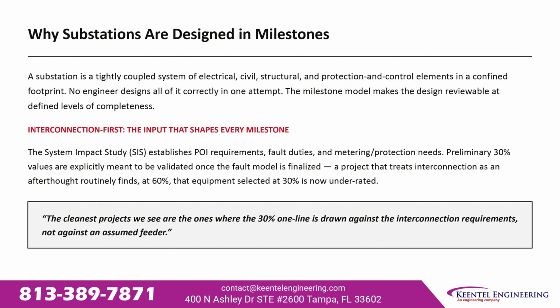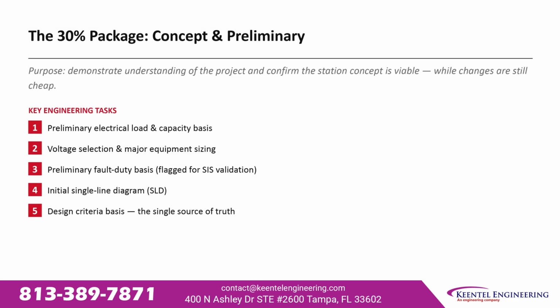The input that shapes every milestone is the interconnection. The System Impact Study establishes point of interconnection requirements, fault duties, and metering and protection needs. Preliminary 30% values are explicitly meant to be validated once the fault model is finalized. A project that treats interconnection as an afterthought routinely finds at 60% that equipment selected at 30% is now underrated. The purpose of the 30% package is to confirm the station concept is viable while changes are still cheap.